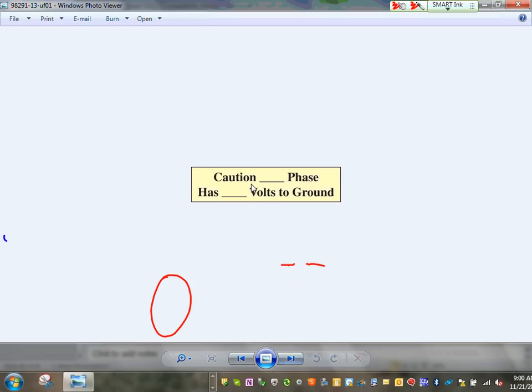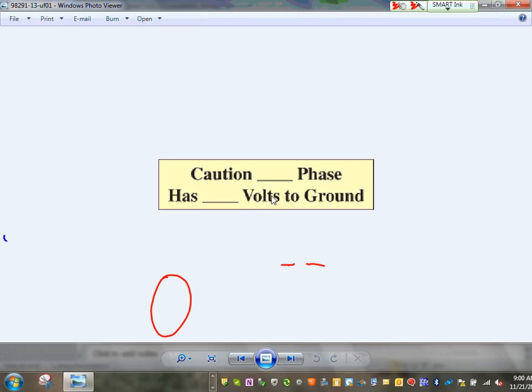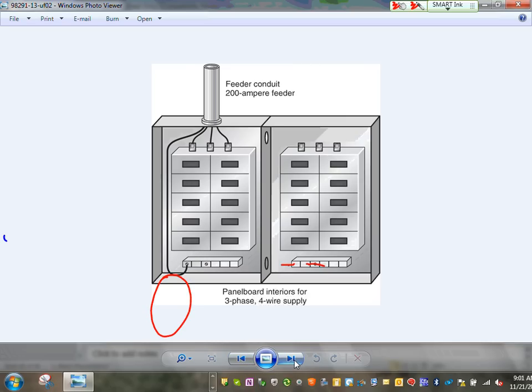You do have to wear, here's Brian, a caution: phase has 208 volts to ground. If you have a high voltage section, you have to have this label right at the 480, I'm sorry, 240, 120 center tapped delta to warn the people, hey, Mr. Apprentice, you shall not connect anything between phase B and the neutral because it's 208. And you put 208 across this, which is rated for 120, you have just burned it. And there's stories after stories of people burning equipment because they did not pay attention to that.